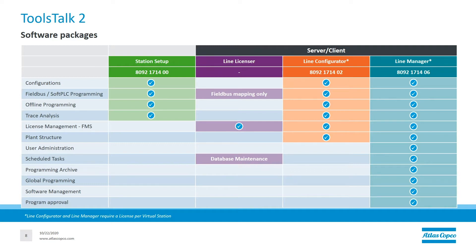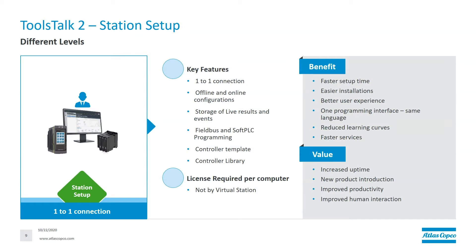The server versions are for multiple users. For Station Setup, this is an offline version of ToolsTalk 2, used to configure a controller in a one-to-one connection. You could do offline and online configurations — your controller could be saved in Station Setup and you can view it offline later and make changes. You could also have up to 250 live traces for comparison, field bus and soft PLC programming, and you could create a controller template and distribute it to different stations. This is licensed per computer, so if you have three computers with three different MAC addresses, you need three licenses of Station Setup.